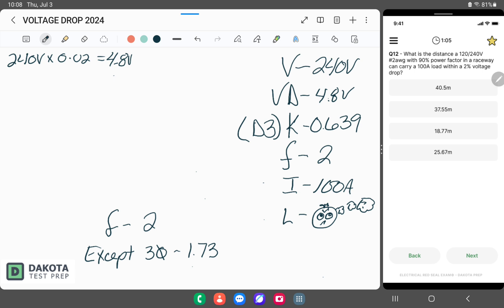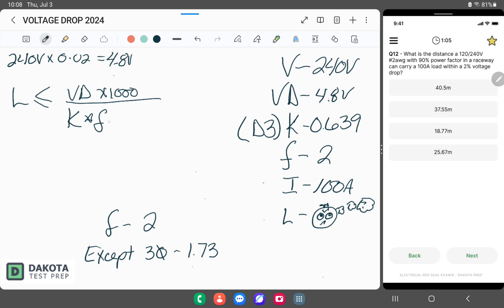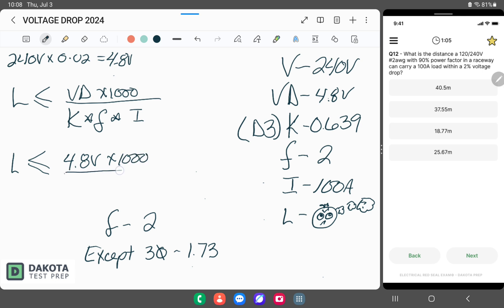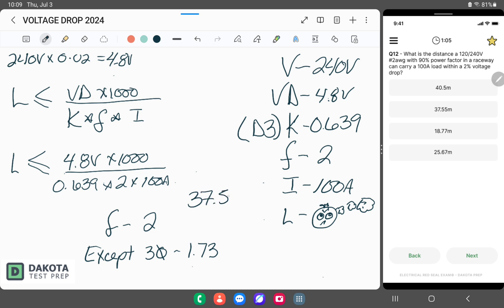Now we have all our variables, so we just pop them into our formula for length. Length is less than or equal to voltage drop times 1,000, divided by K factor times F times I. So: L ≤ 4.8 × 1,000 / (0.639 × 2 × 100). Once we do all the math, we end up with 37.55 meters.